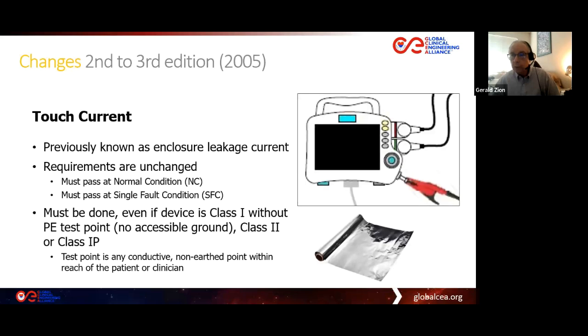Okay, I talked about touch current, but I want to cover here, what if there is no non-grounded conductive test point on the medical device? Now remember, this cannot be the protective earth test point. You must have your test probe properly on the proper measurement location. And this test must be done no matter what. We have to run this test, even if there's no ground.